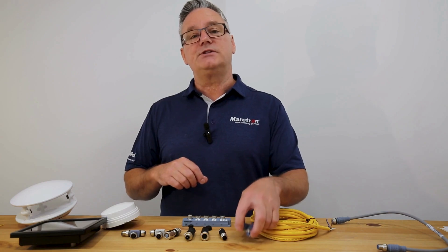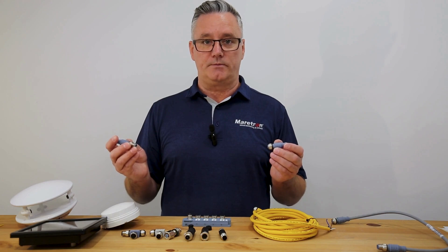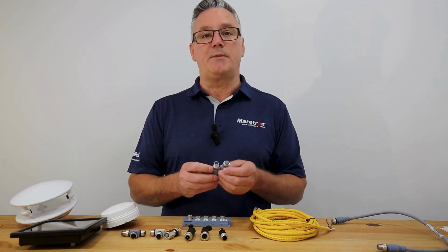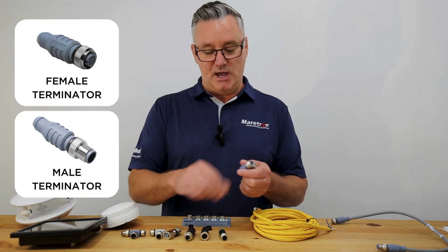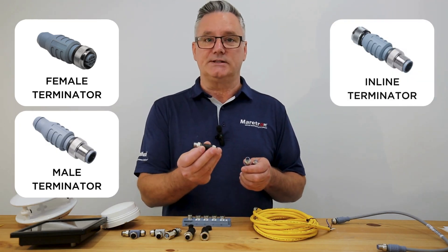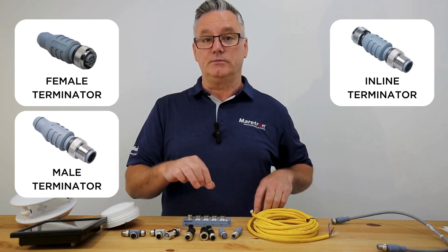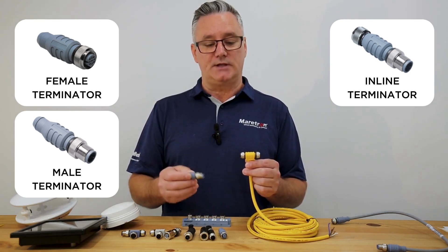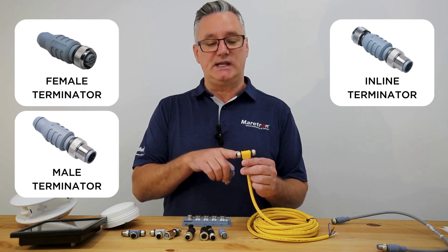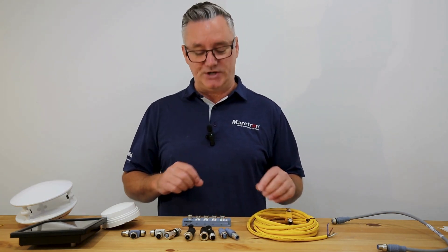We then have terminators, and terminators go to each end of the network. These terminators come in three different types: a female type, a male type, and what's called an inline terminator. On a Maretron network we would use male connectors at both ends, and the reason for that is because the power T is female on both sides — so that's something to watch out for.